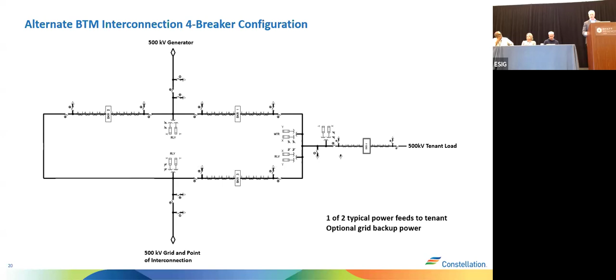And we have the ability so that if the power plant goes out of service, the 2 circuit breakers at the top of that ring bus open, and power is still able to be fed backwards from the grid to the tenant in this case. But you can set up your protective relaying such that it either will or will not be fully isolated from the grid in this type of a condition. And some of the customers that we're working with want to have power that's able to flow backwards from the grid under certain circumstances.